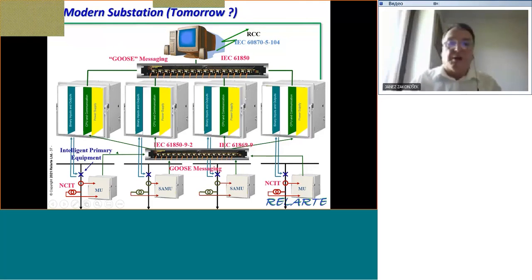Now coming to process bus: if you have a big substation, say 20 or more bays on a certain voltage level, even modern communication capabilities cannot manage the communication necessary, for example, for busbar protection. So that is still a bit of an issue, but I will show you some others.